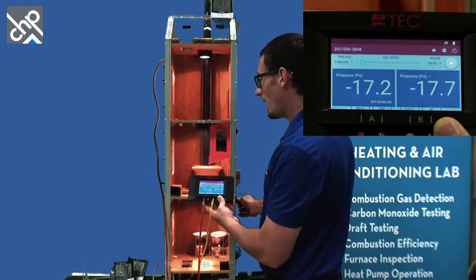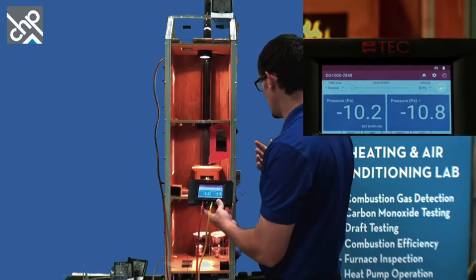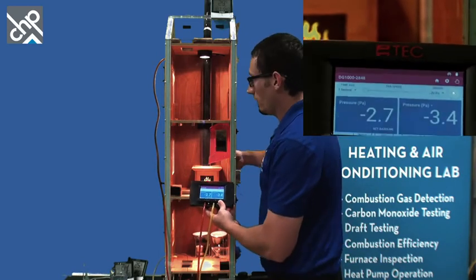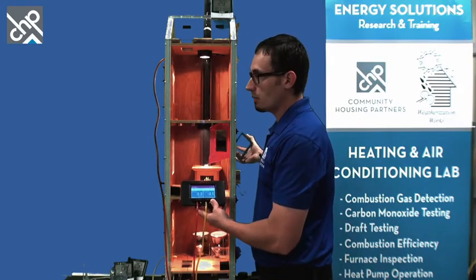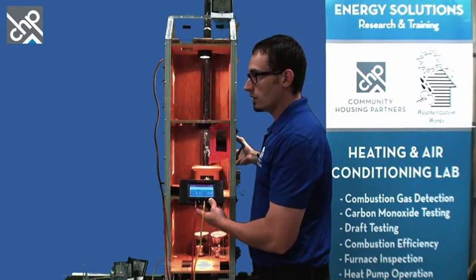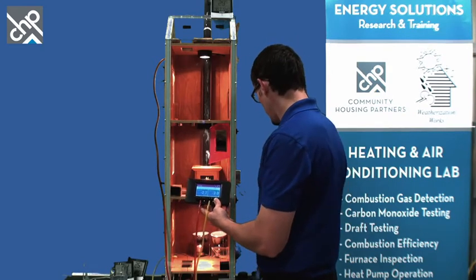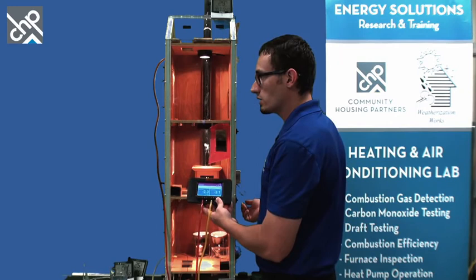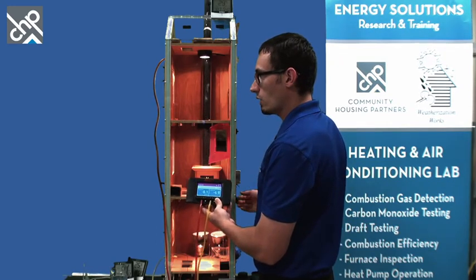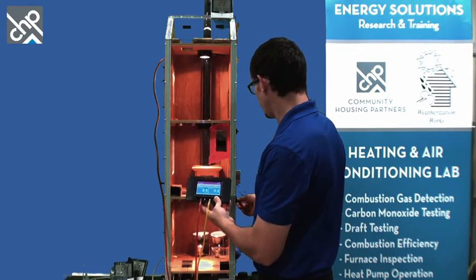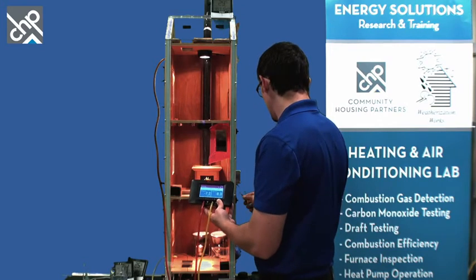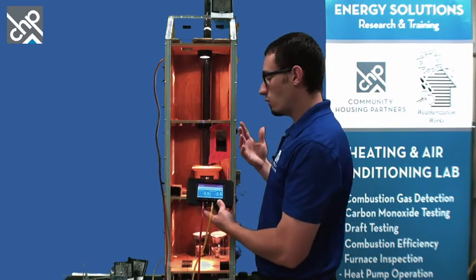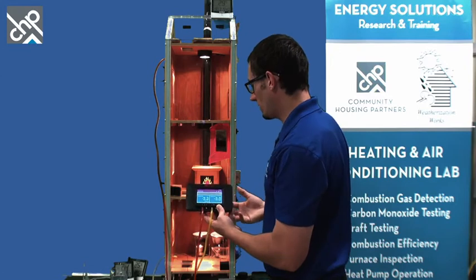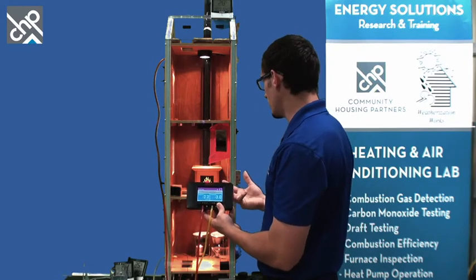So why exhaust? That's maybe the first question. So again, one of two options. I provide makeup air directly to the appliance and everything works. Even if I were to crank up the pressure on the fan, everything's still going to work as intended here. If not, well, why ventilation? Why exhaust ventilation? We know we need ventilation originating from outside, but why exhaust?